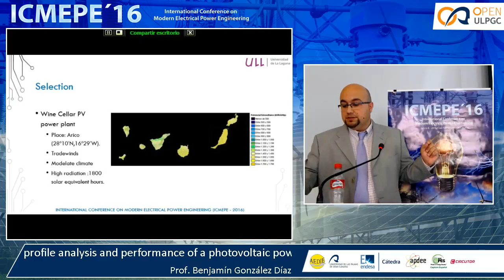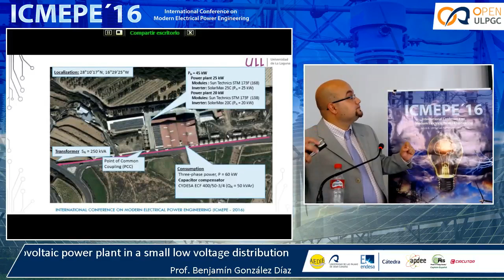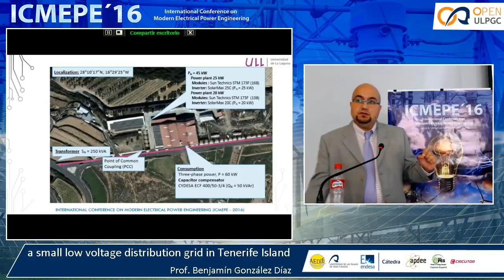So this is the power plant. It is placed on the roof of a wine cellar. This is the location. The transformer is through this line. There are more or less 940 meters from the transformer to the point of common coupling. The wine cellar has a three-phase consumption with a nominal power of about 60 kilowatts, and it also has a capacitor installed with a power of 50 kilovolt-amperes reactive.